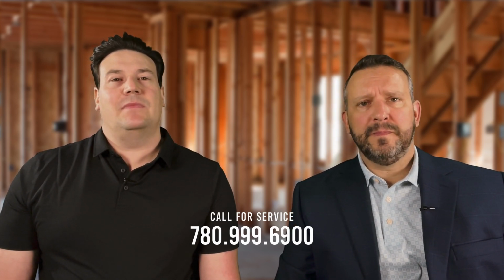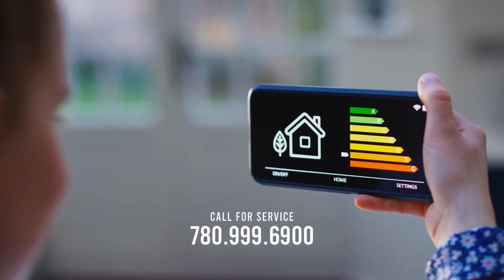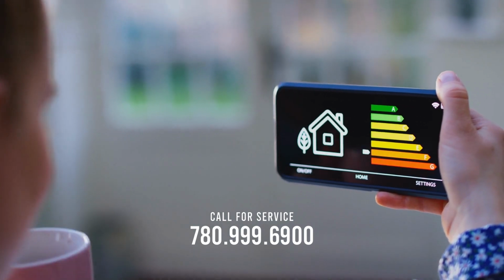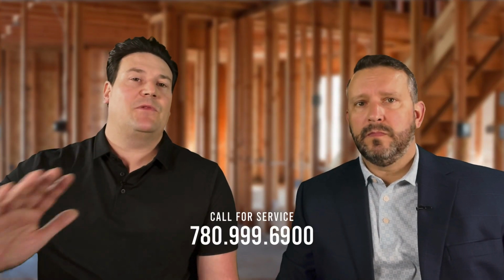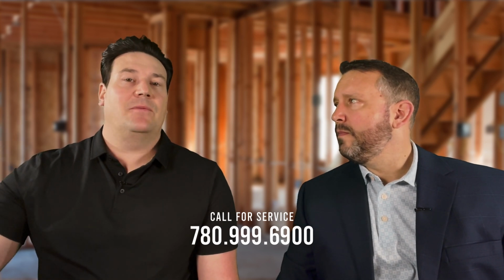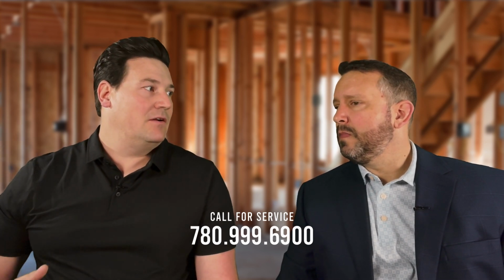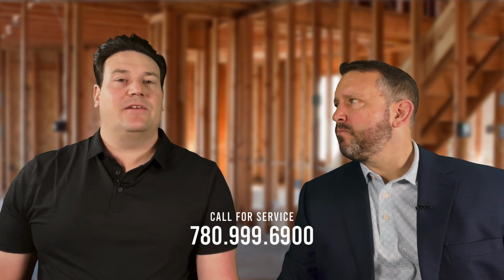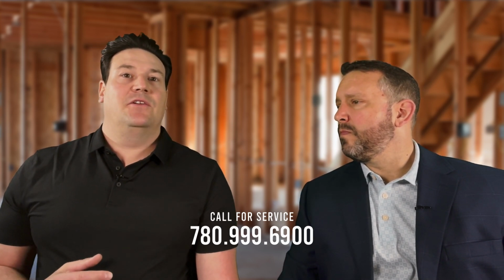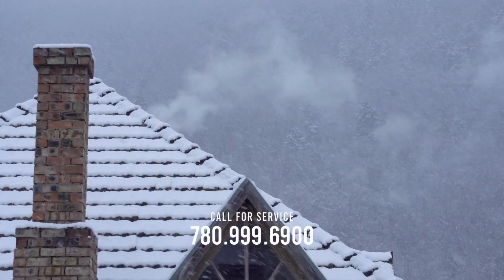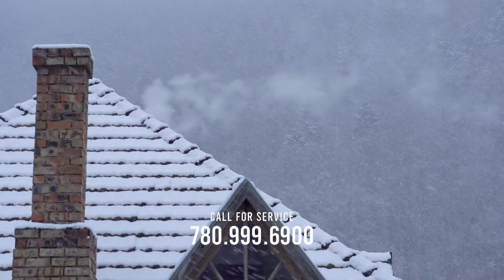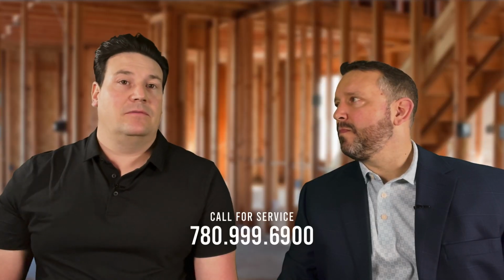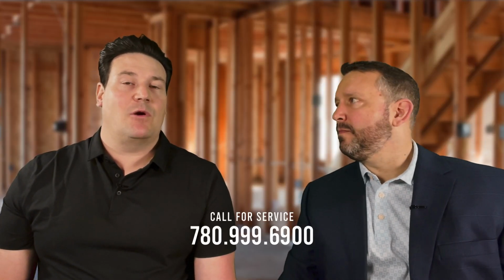Are they very common? Why would somebody need an HRV? Probably the most important reason first is to save energy, by using the fresh air or stale air that we're removing from the home. We're going to take the heat from that air and add it to the incoming fresh air. So instead of having your furnace warm up air that's minus 30 here in Alberta, or minus 40 sometimes, it's going to be warming up warmer air already. So it takes fewer BTUs to warm up that air initially.